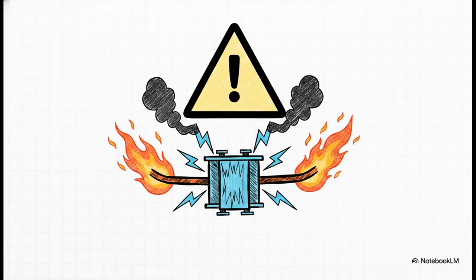We've talked a lot about the magic of the physics and the brilliant engineering, but working with this equipment is inherently dangerous if you don't know the rules. So we really must pause for a very serious, practical warning: safety first. You must never, ever short-circuit the secondary of a potential transformer. Now, in the world of electrical engineering, you have current transformers, where the secondary must never be left open. Well, the potential transformer is the exact opposite. If you short-circuit a PT's secondary, the device will desperately try to maintain the voltage by drawing an absolutely massive, overwhelming flow of current. The result? It'll immediately blow safety fuses, permanently fry those delicate windings, and completely destroy an incredible piece of equipment. Basically, respect the physics, and the physics will work for you.